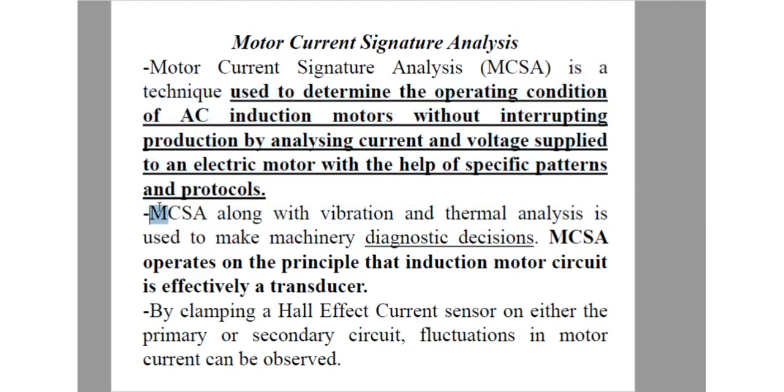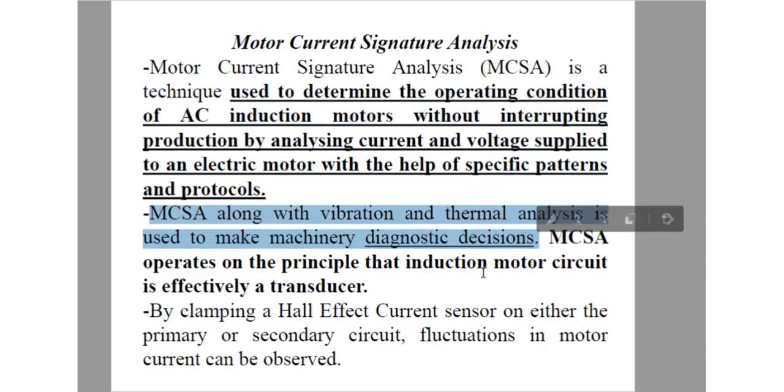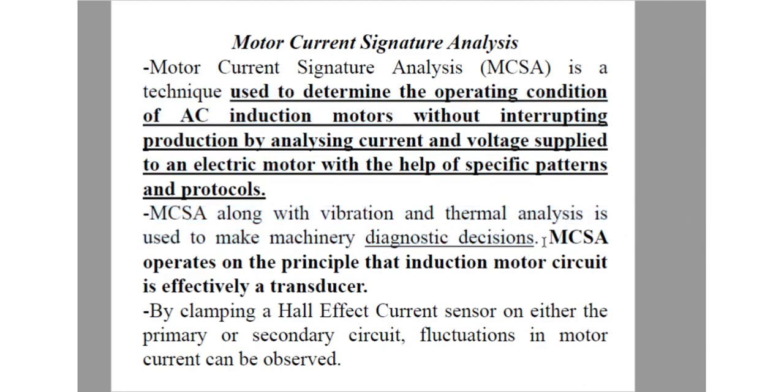MCSA, along with vibration and thermal analysis, is used to make machinery diagnostic decisions. MCSA operates on the principle that an induction motor circuit is effectively a transducer. By clamping a Hall effect current sensor on either the primary or secondary circuit, the fluctuations in the motor current can be observed.